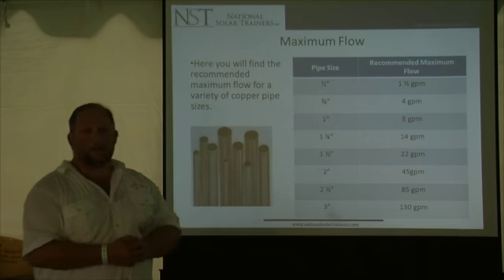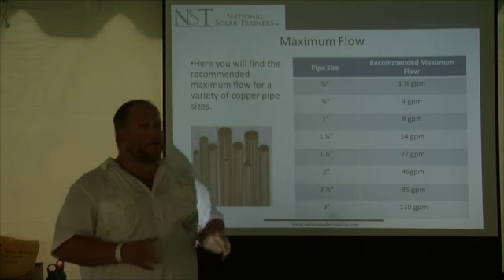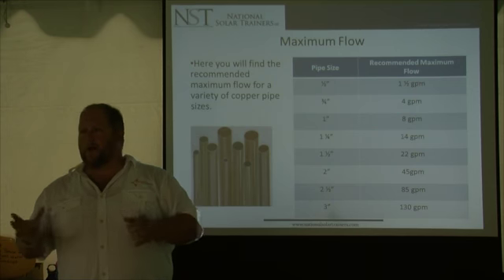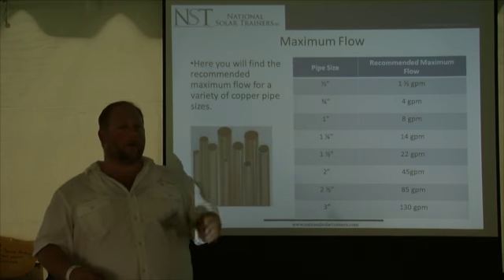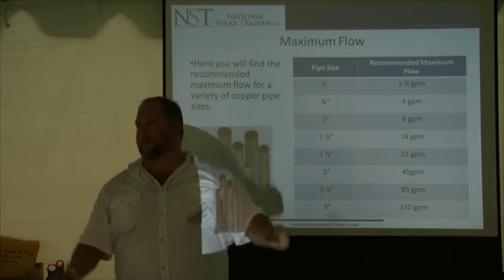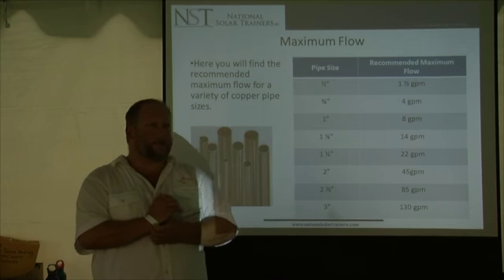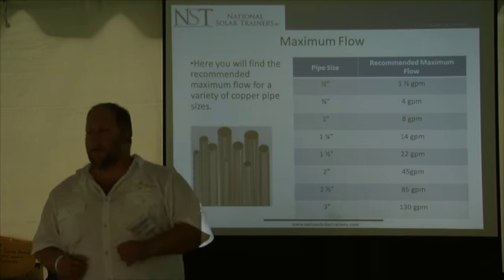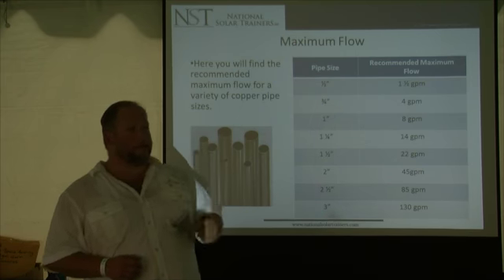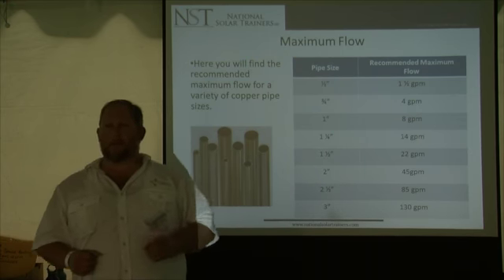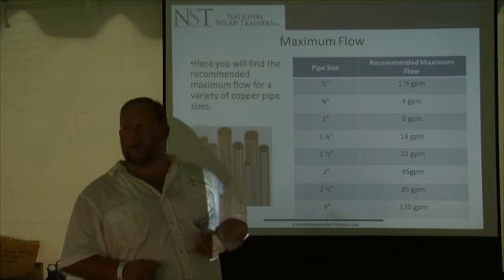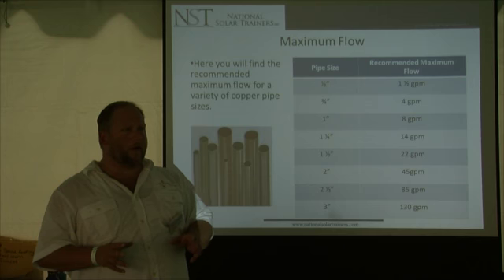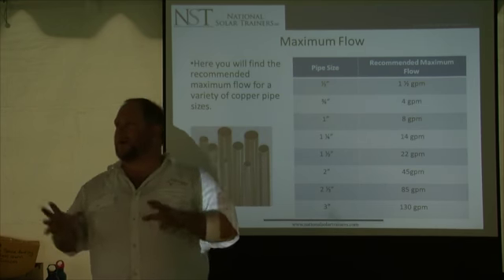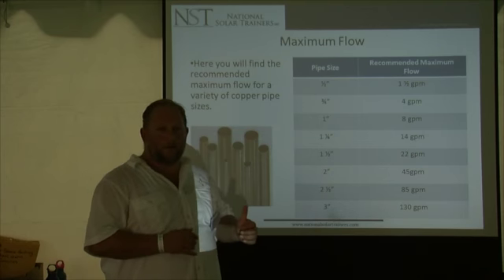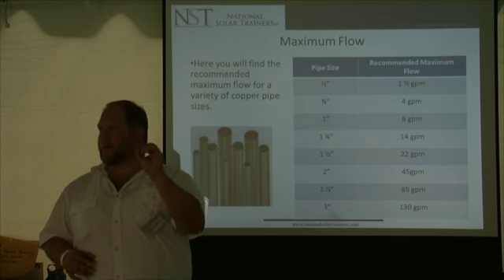Okay, now, what size diameter pipe do you use? Well, that's dependent on the square footage of collectors. One thing you have to be careful about is you can't say you've got a 3 collector system or a 7 collector system or 8 collector or 1 collector. How big is it? It's a 20 square foot system, a 40 square foot system. With thermal, I can't just say it's a 1 kW, 2 kW, 4 kW, and you can't say a 3 collector system, because you've got 20 square foot collectors, 30 square foot collectors, 28 square foot collectors, 21.75 square foot collectors. So the square footage is what's important, not the number of collectors. The square footage of the system is what will determine your flow rate. The flow rate is what will determine your pipe diameter.